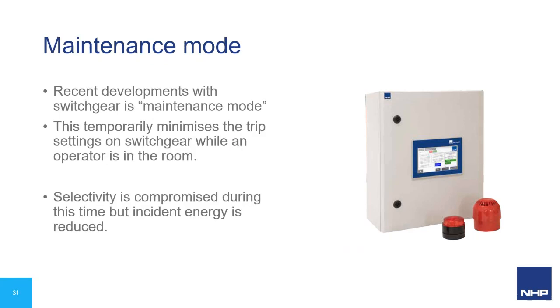An extension of that industrial comms is what we call maintenance mode. That's where you can remotely minimize the trip settings on the switchgear while the operator is in the room. Going back to selectivity, that's completely compromised during this operation, but the idea is that you're putting safety in front of selectivity as a priority. So while somebody's in the room, you might get a nuisance trip on the ACB rather than the actual correct gear downstream, but that's something you live with.